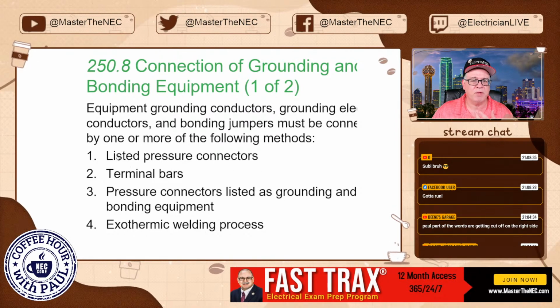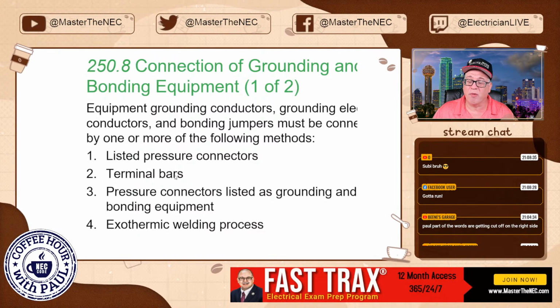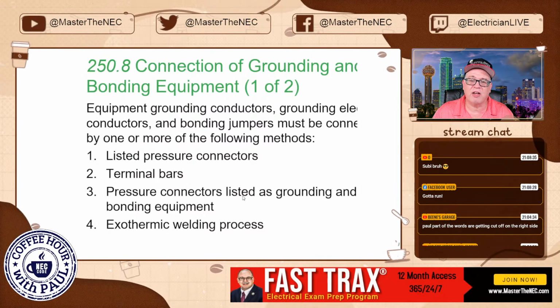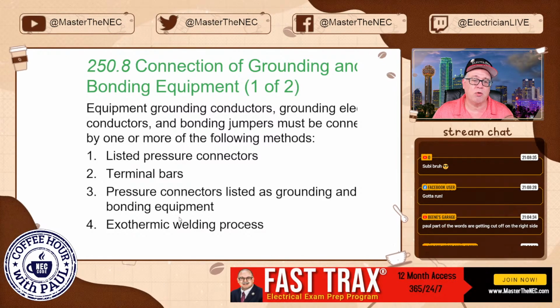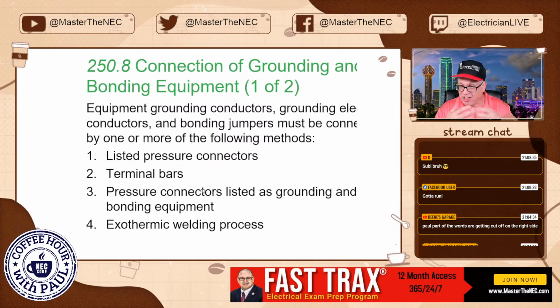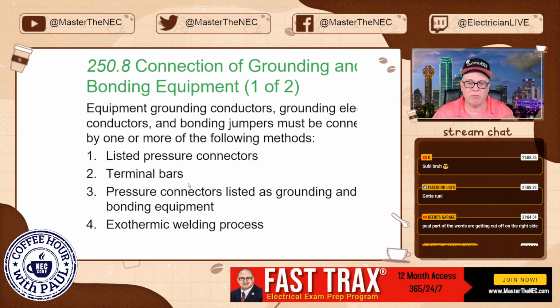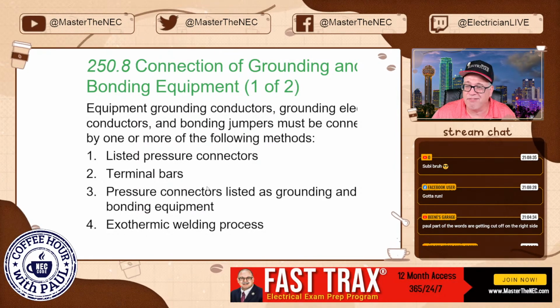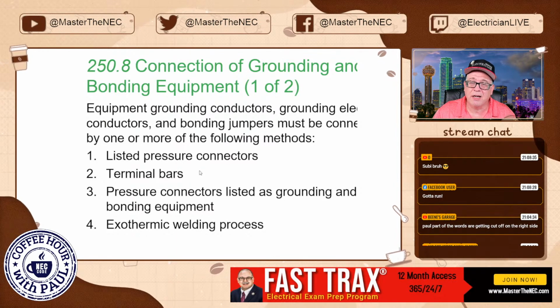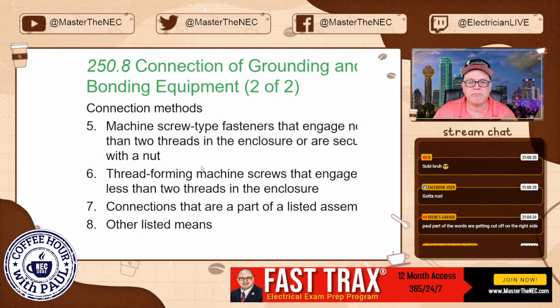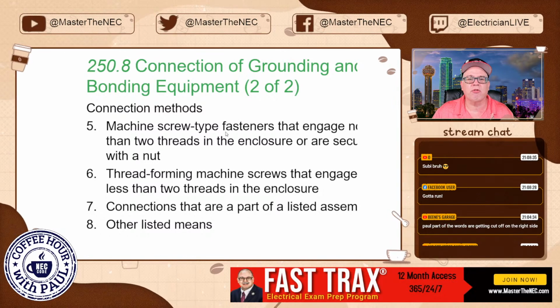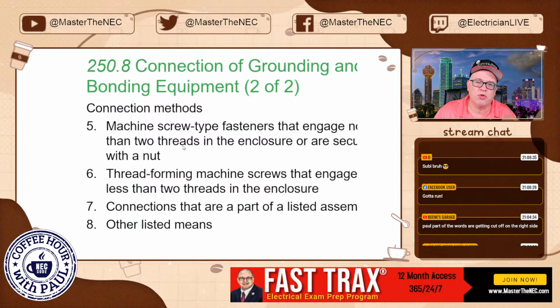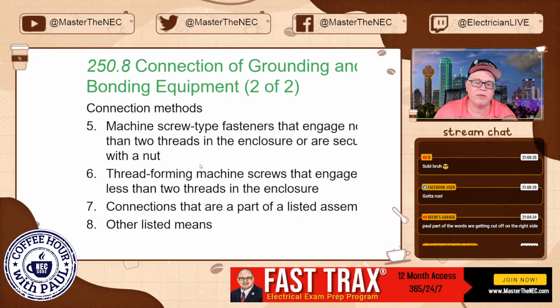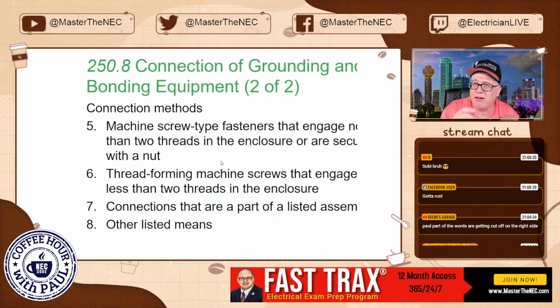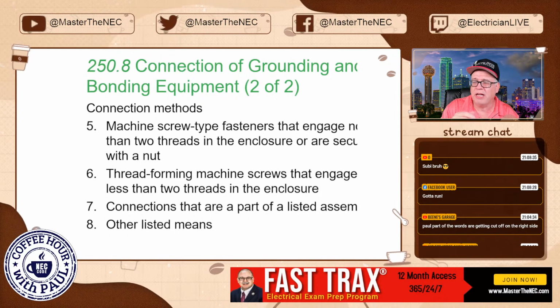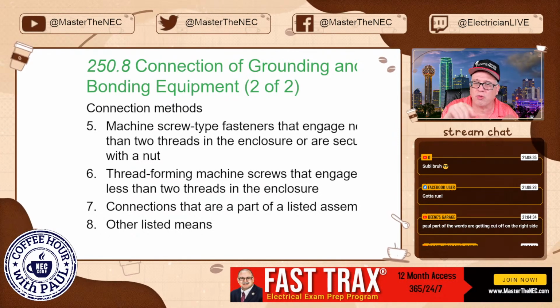You can use any of these if you want, and multiples of these if you want, by one or more of the following methods: listed pressure connectors, terminal bars, pressure connectors listed as grounding and bonding equipment, exothermic welding. If you've ever done exothermic welding, that's where they actually have a chemical reaction. A lot of times this is done on communication towers and things like that. Machine screw type fasteners engaged not less than 2 threads in an enclosure or secured with a nut. So if you've ever looked at the back of your panel enclosure where that green screw goes into it, you're going to notice that it has to engage at least 2 threads.